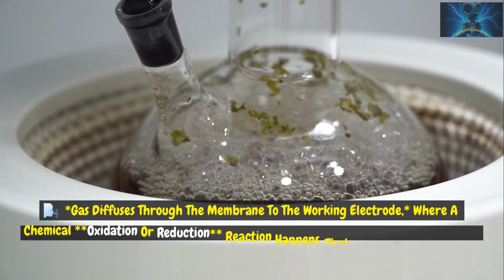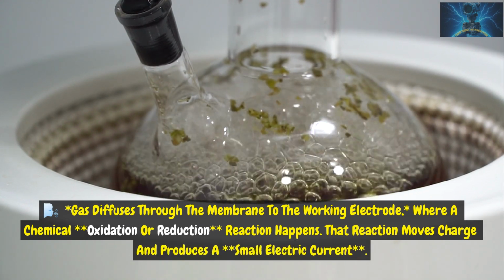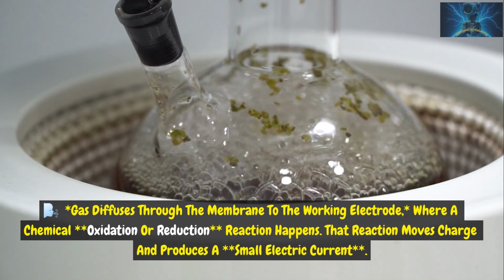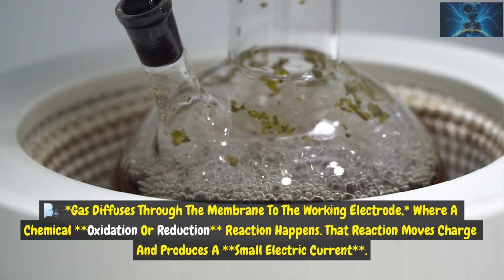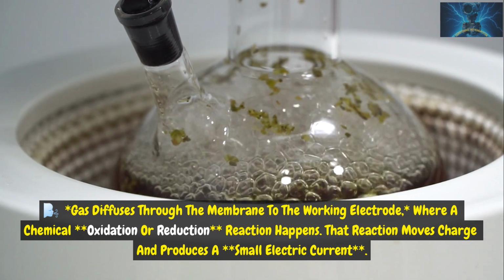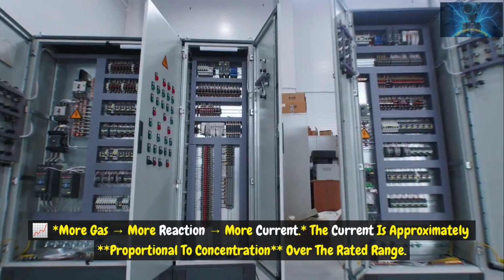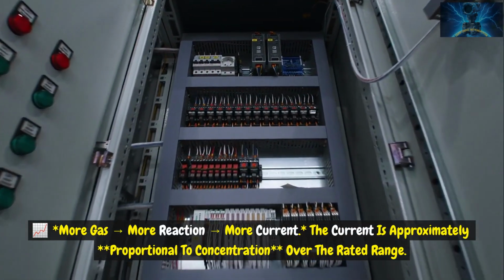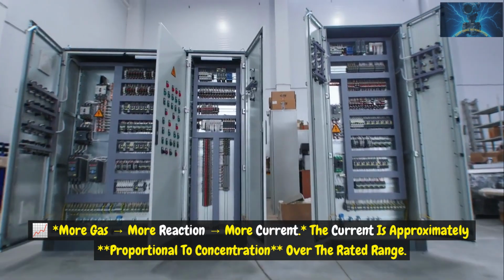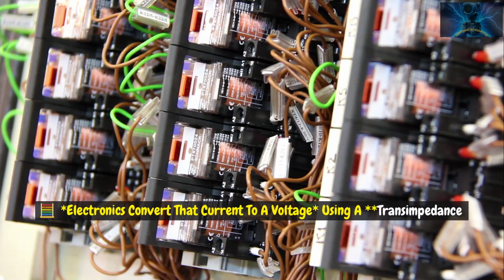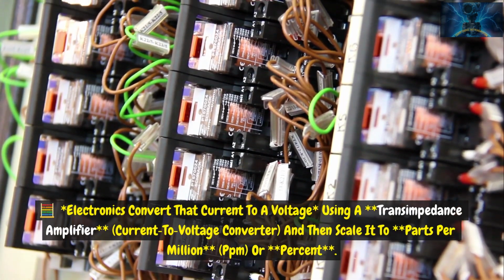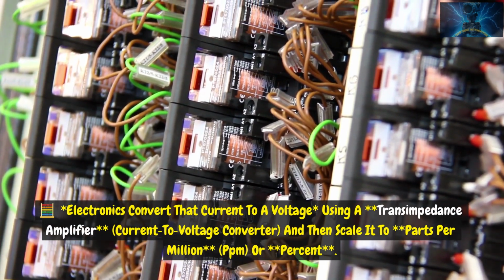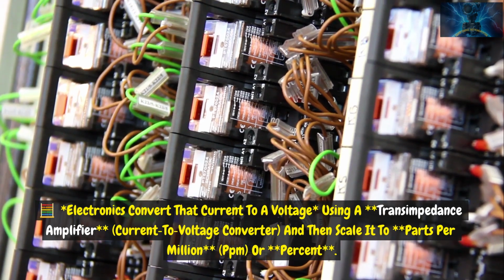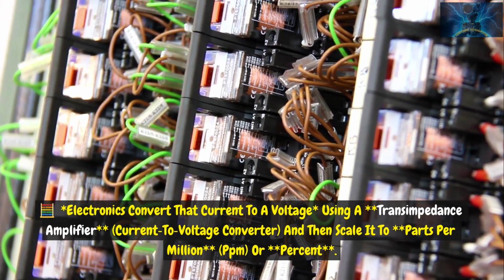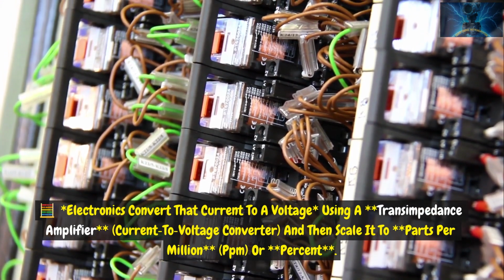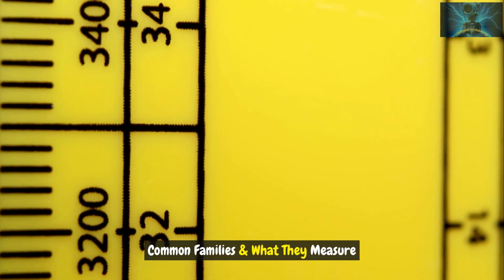Gas diffuses through the membrane to the working electrode, where a chemical oxidation or reduction reaction happens. That reaction moves charge and produces a small electric current. More gas, more reaction, more current. The current is approximately proportional to concentration over the rated range. Electronics convert that current to a voltage using a transimpedance amplifier, a current to voltage converter, and then scale it to parts per million, ppm, or percent. Common families and what they measure.